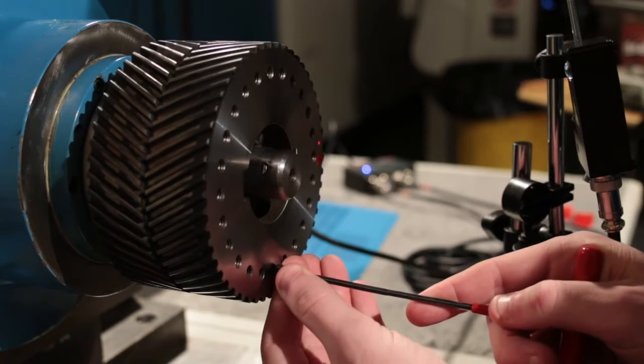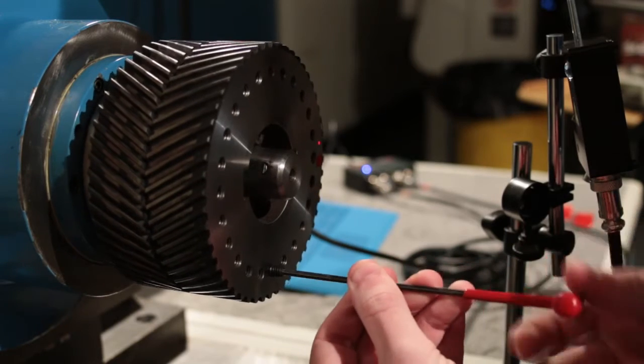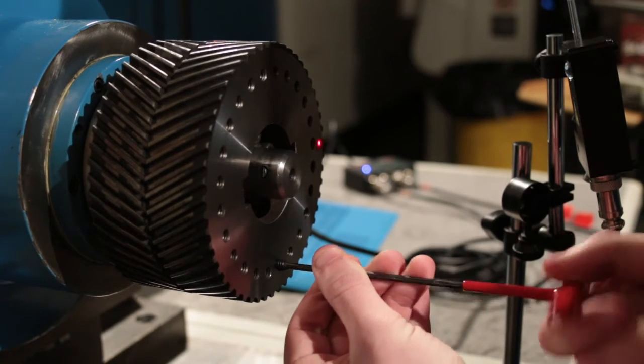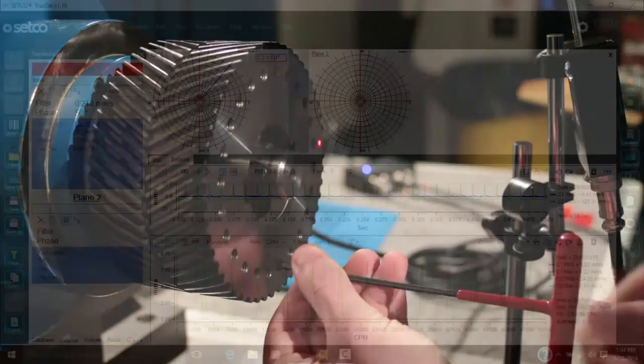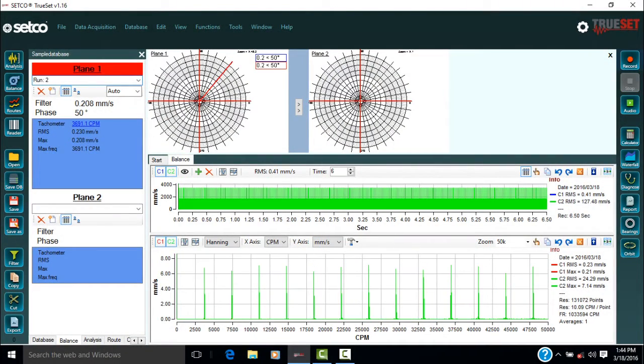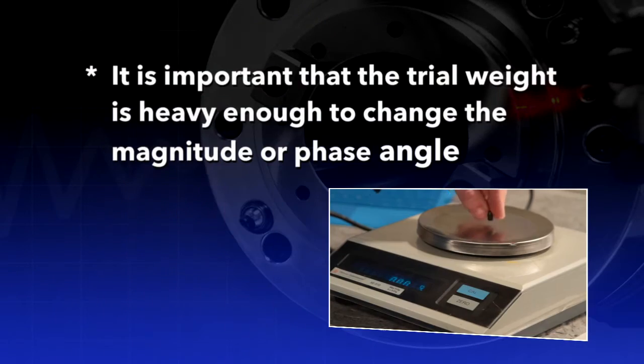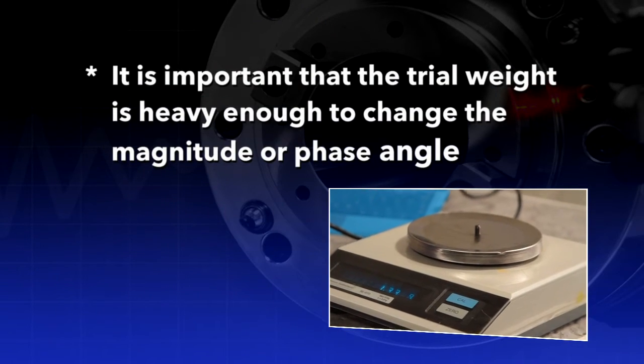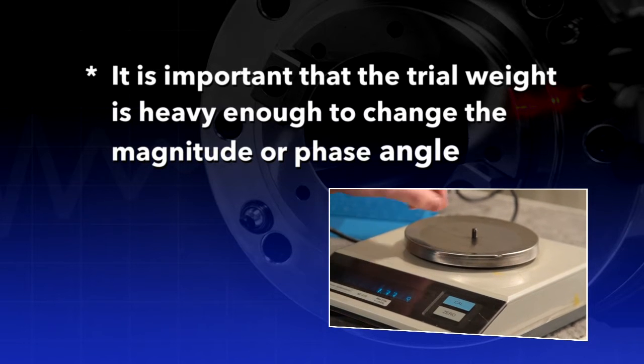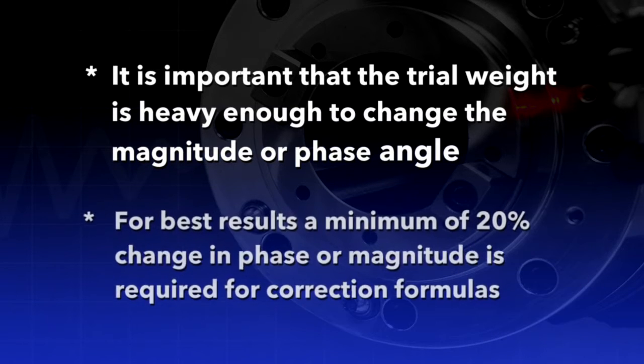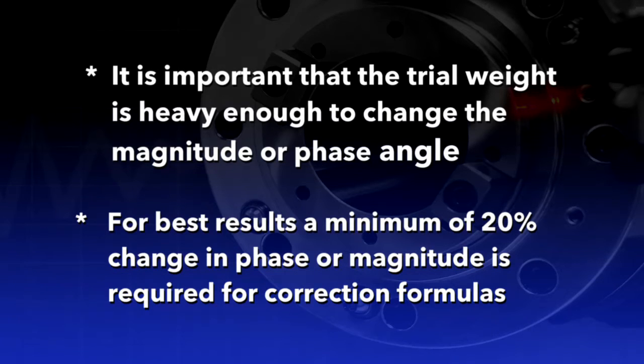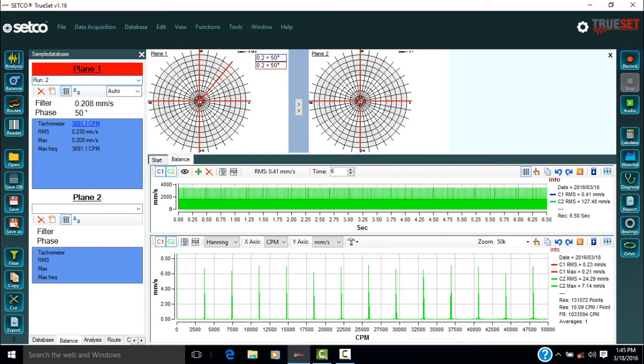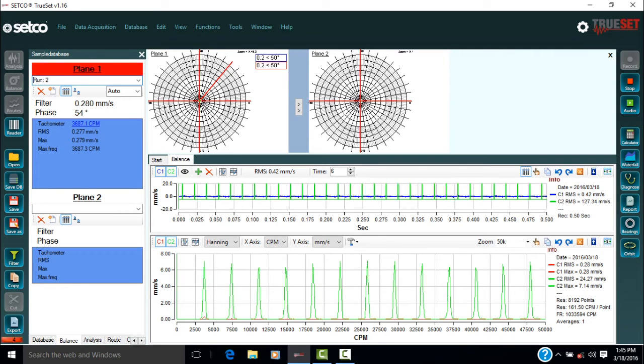Now add or remove a known weight in a known location and take note of the angular location relative to the zero degree point in the polar graph. This is the trial weight. It is important that the trial weight is heavy enough to cause a significant change in either magnitude or phase angle. For the best accuracy, a minimum of a 20% change in either phase or magnitude is required for correction formulas. Press the record button again with the equipment running to get data for calculating the weight required for balancing.